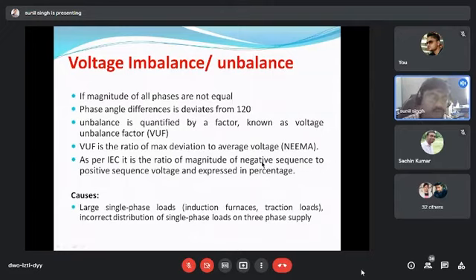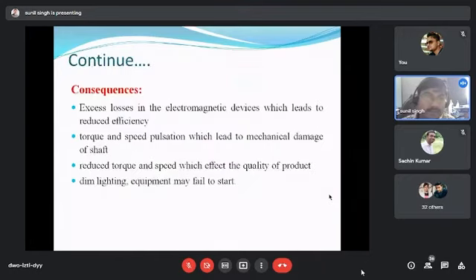But nowadays some researchers are also using the complex VUF, which takes the magnitude as well as the angle. So this is all about the voltage unbalance factor. It is very important related to voltage unbalance. What is the cause of this voltage unbalance? Large single phase loads. Mainly the main cause is the incorrect distribution of the single phase load, or a fault. If a fault occurs in one phase, then the supply can be restored from the other phase, so it may also be a cause of the voltage unbalance.